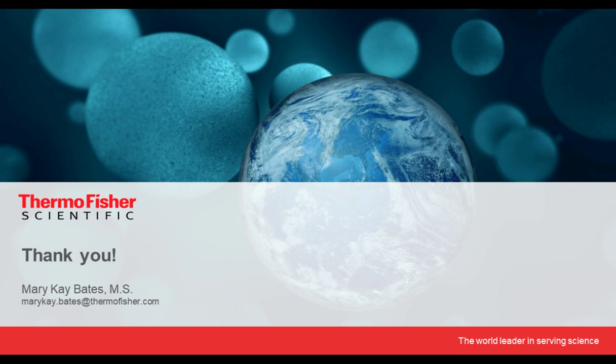They've gotten pretty harmonized in that instead of, for example, for heat sterilization, they used to recommend a given temperature and time, so 160 degrees for 2 hours, and that would constitute sterilization. But it's now recognized that if you don't reach that given temperature, microorganisms may survive because they're not actually at 160 degrees for 2 hours, for example. So now the pharmacopoeias recommend or require proof of sterilization using 1 million organisms, resistant bacterial spores, which are proven to have a specific D value, and I won't go into what that all means right now, but my point is that sterilization is now defined as elimination of 1 million resistant microorganisms, and those microorganisms are specified biological indicators. So look for a process that has been independently tested to verify that it meets that sterilization requirement.